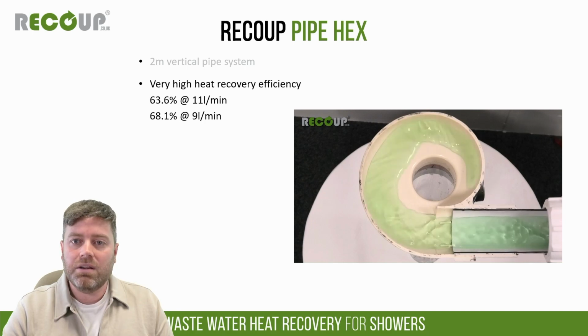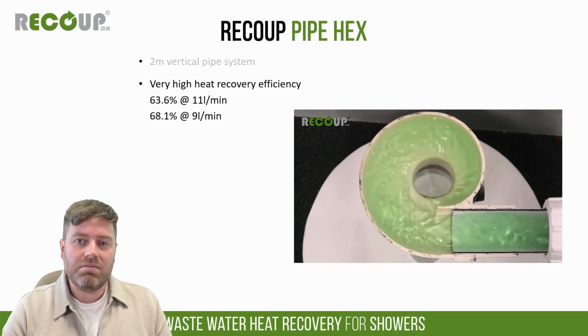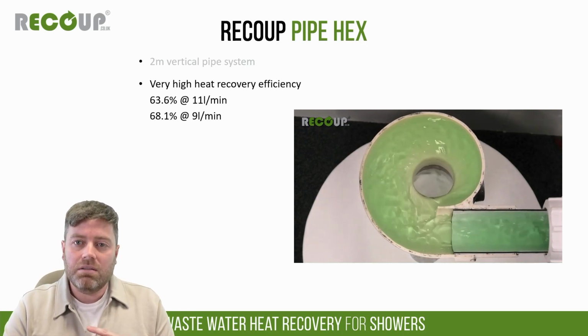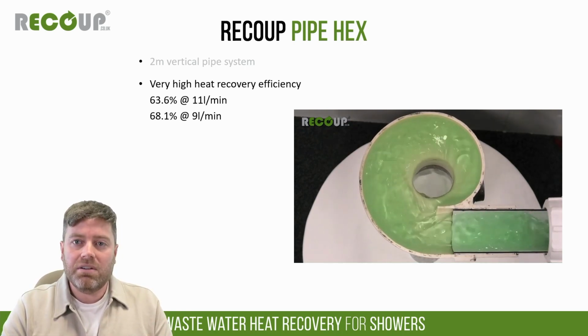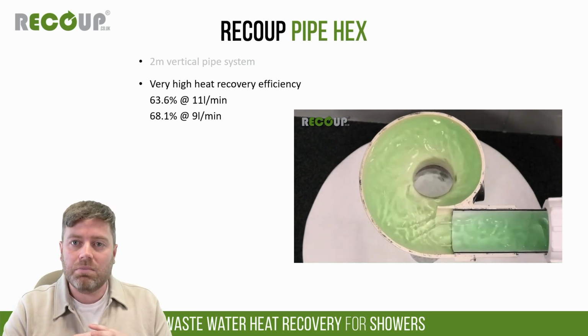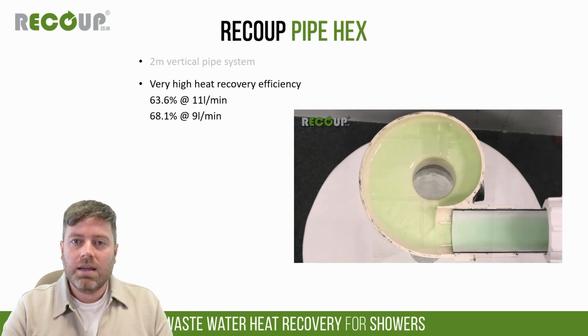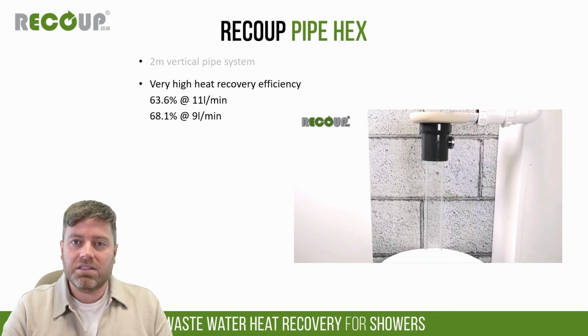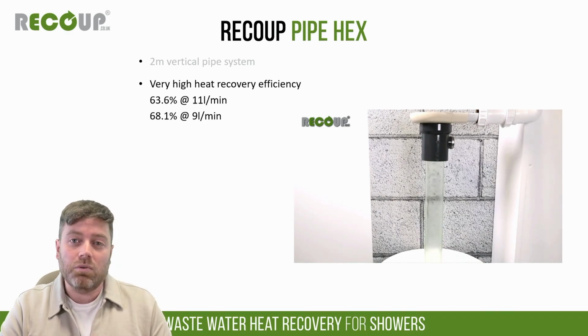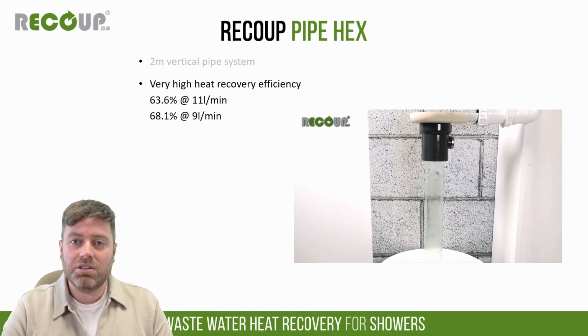And hopefully this video will play. Yes, it is. So this is a turbo rotator cut open, so you can see it from above. You can see the wastewater as it goes down the turbo rotator, makes it spin round in a cyclonic motion, and it clings to the inside of the heat exchanger. Obviously here we've replaced the heat exchanger with a clear plastic pipe, but you can see how we get that sort of thin film heat exchange as it clings to the inside. It also means we don't get any falling water noise or anything like that, because it's not just dropping down the middle of the heat exchanger, it clings to the inside as it rotates round.